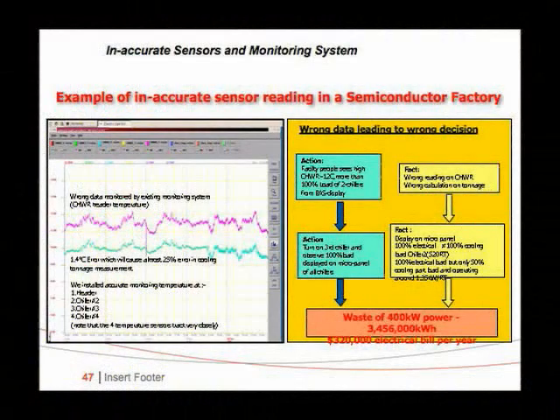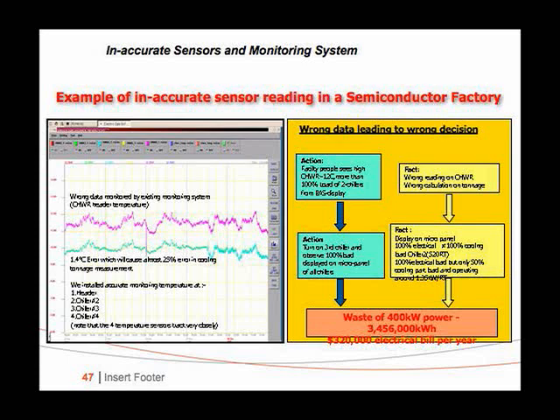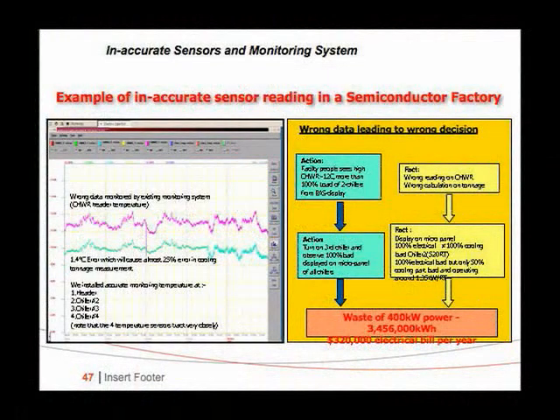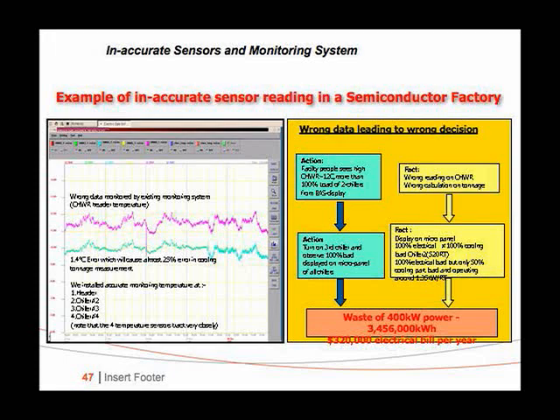We've tested. You would think the semiconductor boys are more interested in accuracy because of ISO 9000 and all kinds of requirements for environmental conditions, and yet here's a new fab. Chill water supply is used as control methodology. This is their building automation, which is new, and this is our audit, which is triple probe, three probes in one sensor, and they are out by 1.4 degree. And you follow the logic, and they are wasting 320,000 Singapore dollars a year, which is $200,000 a year on one probe. And people talk to me about, hey, how come your probe costs $500 more? How do you justify it? Like this?